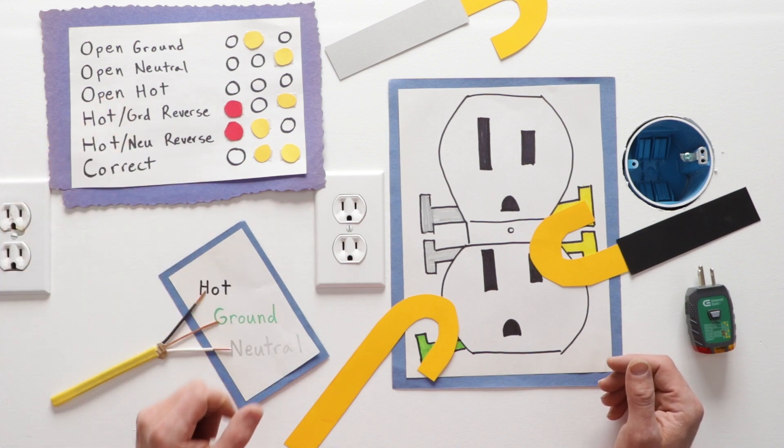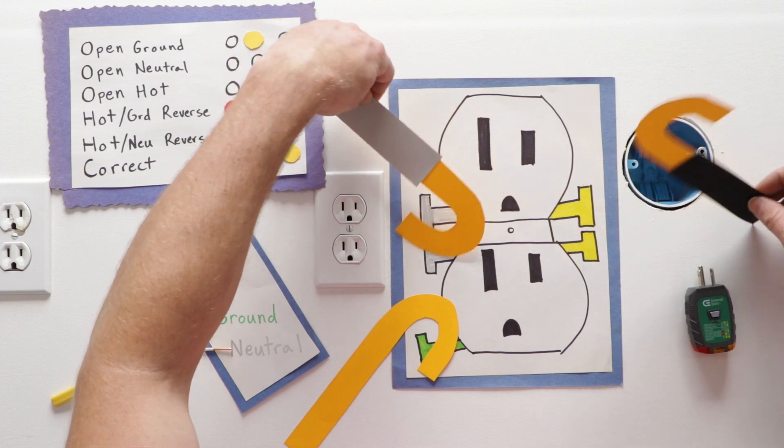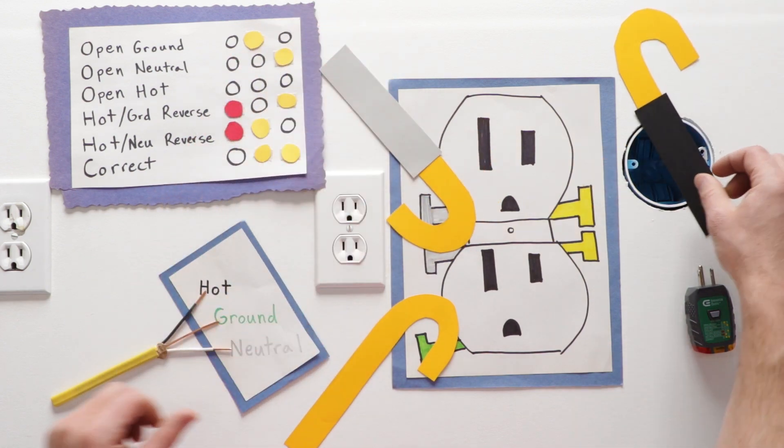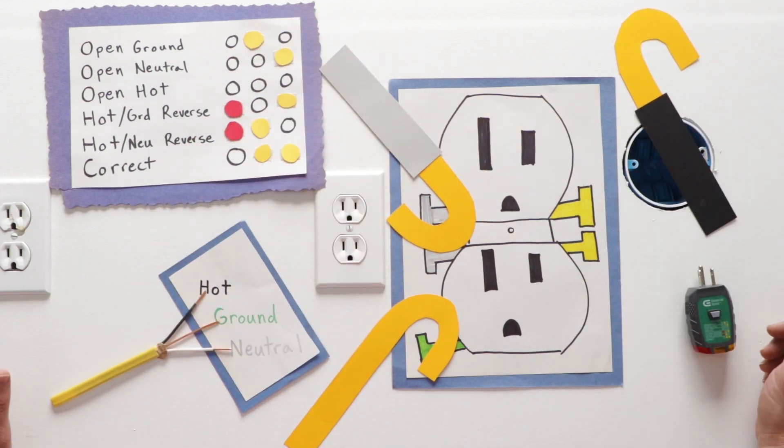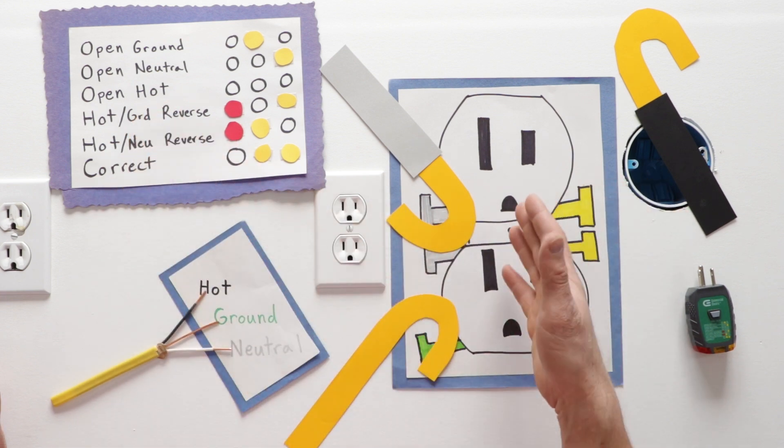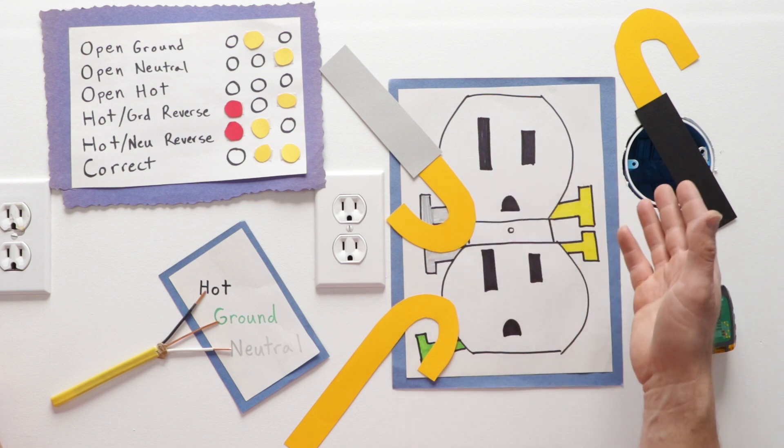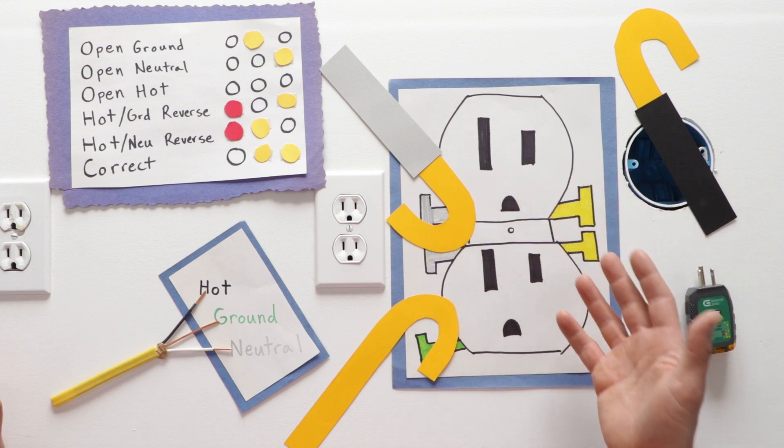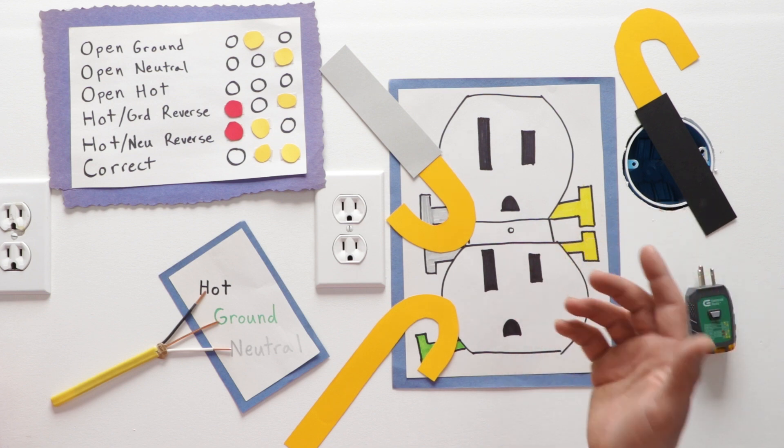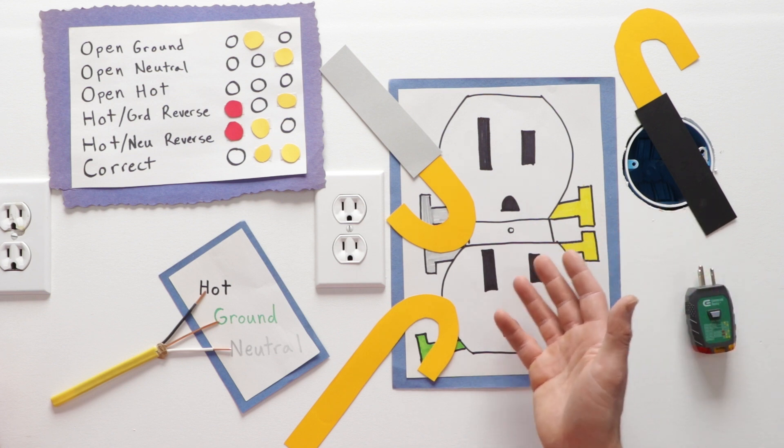Next, we have open hot. That means the hot's not connected. This also could be that there is no power coming to this receptacle because without the hot, there would be no power. So if your receptacle's on a switch or your breaker is tripped, there will also be no electricity.